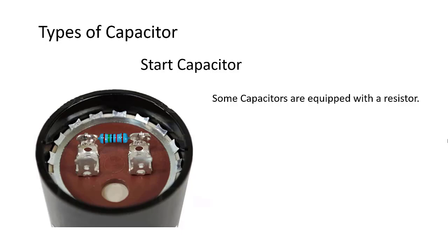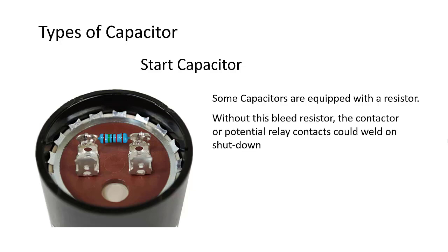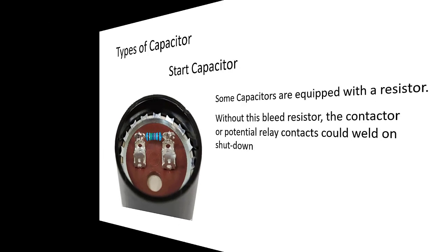Also, start capacitors come with a resistor. Some you can see, like this one, but most often not — it is molded into the cap and you can't see it. This allows the capacitor to bleed down and not weld the contacts in a relay or contactor.